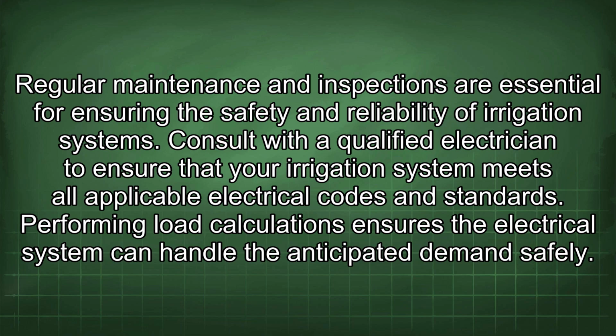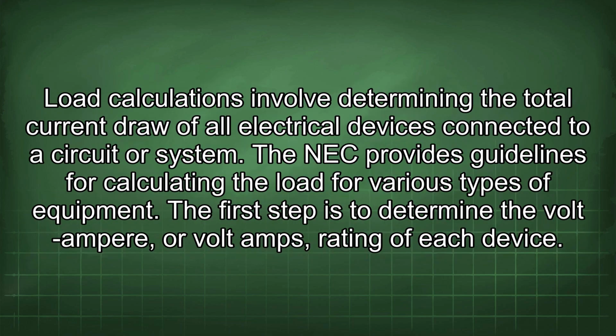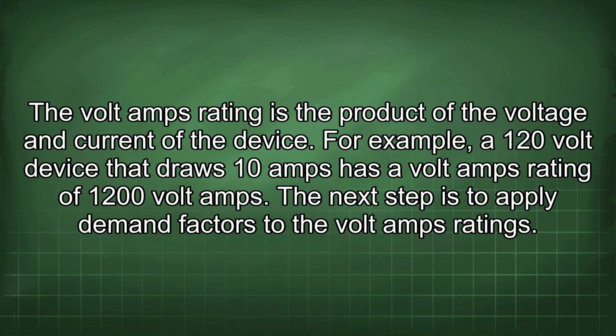Performing load calculations ensures the electrical system can handle the anticipated demand safely. Load calculations involve determining the total current draw of all electrical devices connected to a circuit or system. The NEC provides guidelines for calculating the load for various types of equipment. The first step is to determine the volt-ampere, or volt-amps, rating of each device. The volt-amps rating is the product of the voltage and current of the device. For example, a 120-volt device that draws 10 amps has a volt-amps rating of 1200 volt-amps.